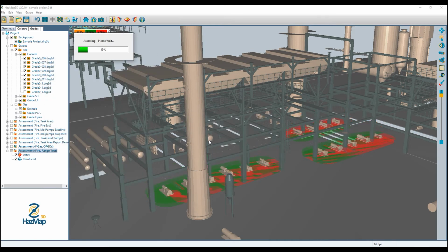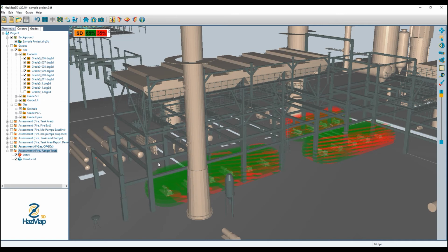And so now at this point, if I have line of sight, I'm seeing all the way to the other end of the bubbles for these pumps, and any additional increase in fire size is not going to improve my coverage at all because I've made it so that I can reach across the entire assessment area with the range of this detector.